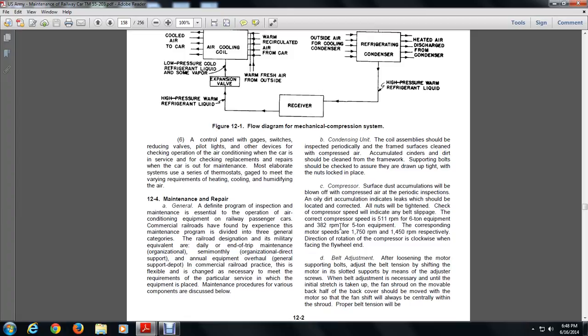Chapter 12-4: Maintenance and Repair. Definition of the program — inspection and maintenance of essential air-conditioning equipment for railway passenger cars. Commercial railways have developed a maintenance program divided into three general categories, with the railroad designating the military equivalents: daily (end-of-trip), organizational/monthly, and annual/general support depot overhaul. In commercial railroad practice, this is flexible and subject to changes as necessary to meet particular servicing requirements. The condenser and coil assembly should be inspected periodically, with fin surfaces cleaned with compressed air.